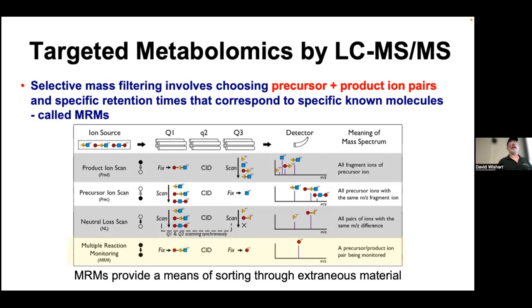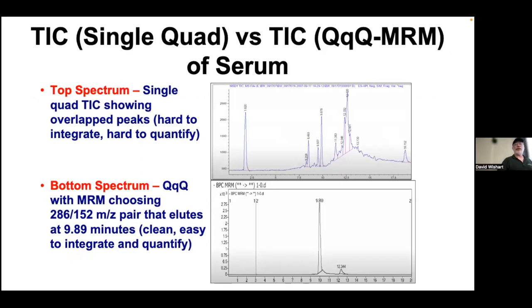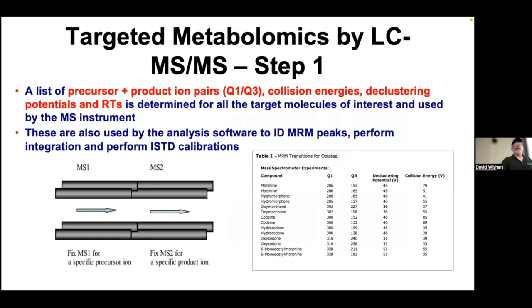Here's a total ion chromatogram from a single quad—pretty messy. If you've done QQQ MRM and chosen just a 286/152 pair at 9.89 minutes, it simplifies to just one peak that you can integrate easily—and that one peak is what allows you to identify and quantify. You need a list of precursor and product ion pairs with their collision energies, declustering potentials, and retention times. If your kit has 140 standard metabolites, you need to determine that for 140 metabolites; if 640, then for 640 metabolites.